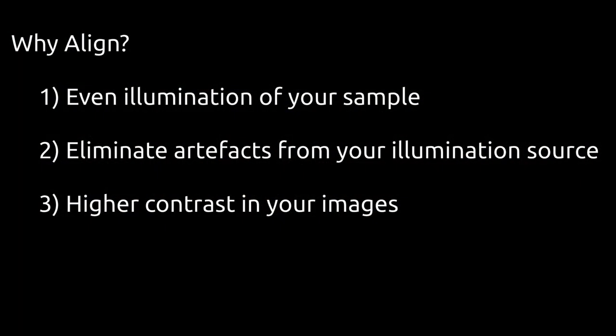Aligning your light source is critical for generating good images. It serves three purposes. It ensures even illumination across your sample. It eliminates any variations in brightness due to the shape of your bulb or filament. And it maximizes the contrast in your image, which is really important when it comes to being able to make out small features like bacteria.